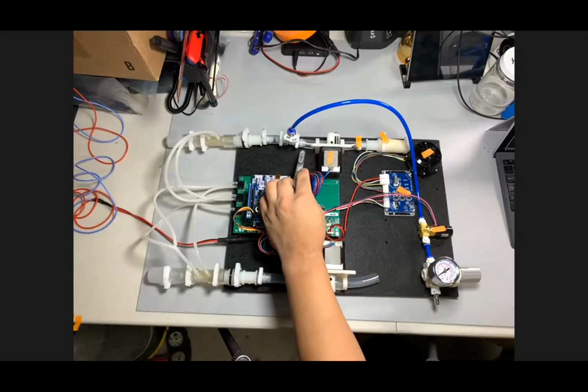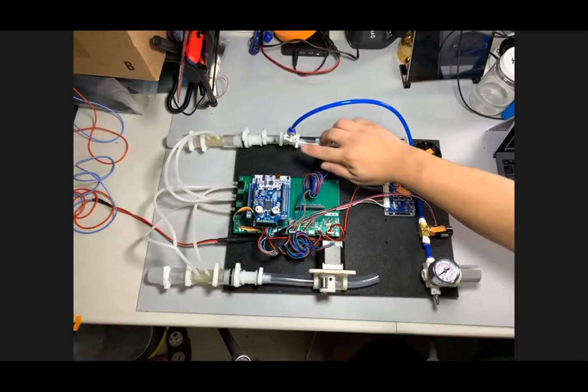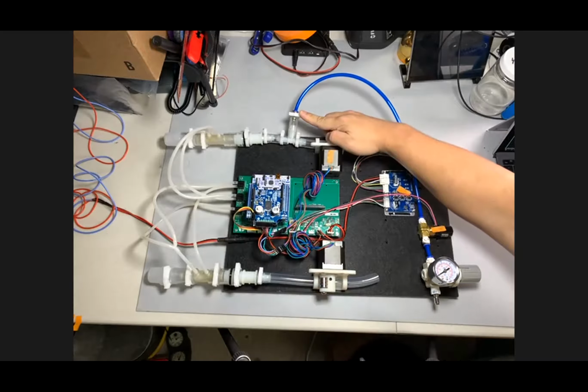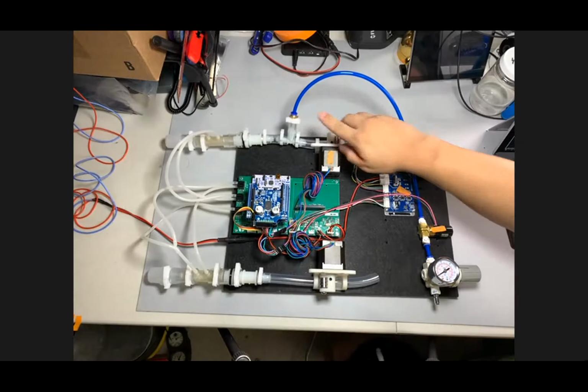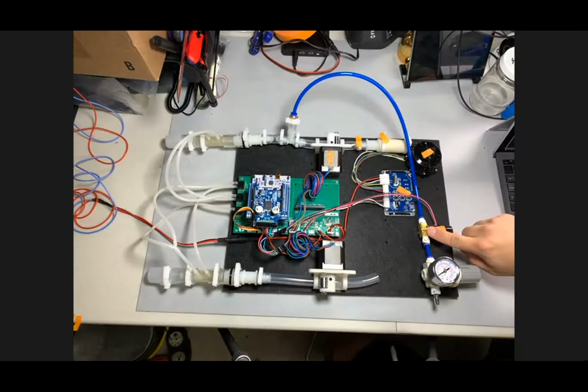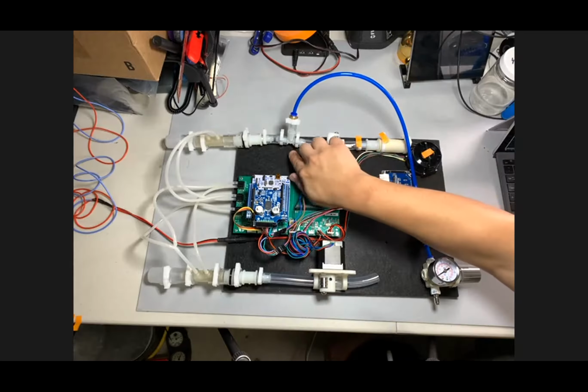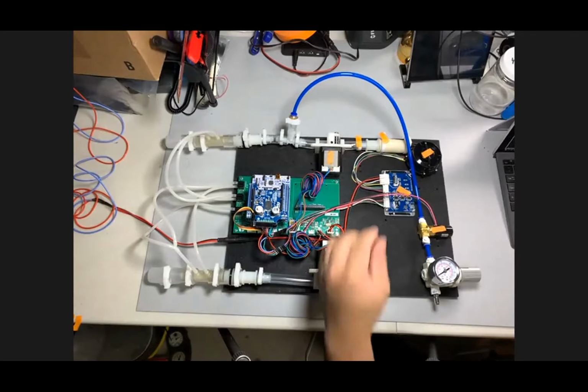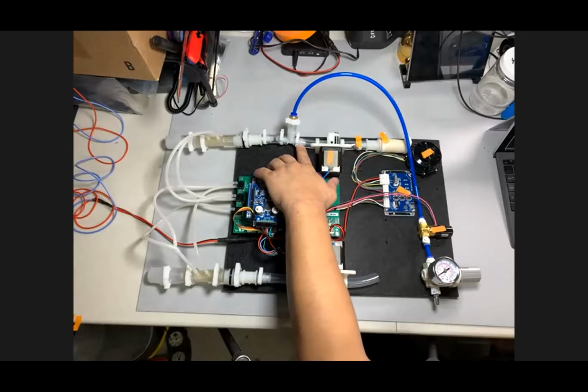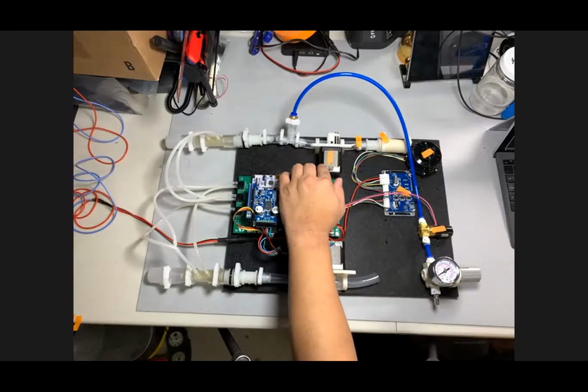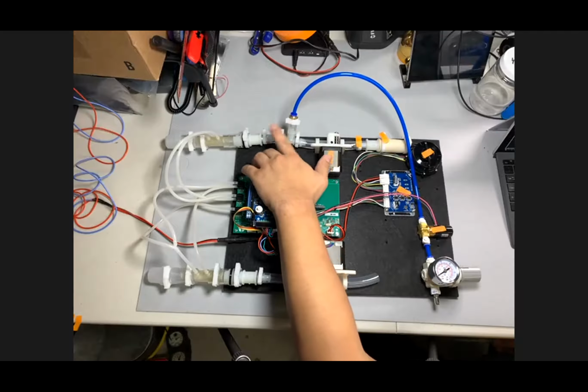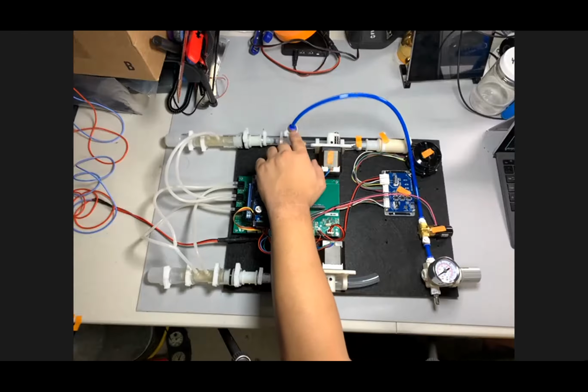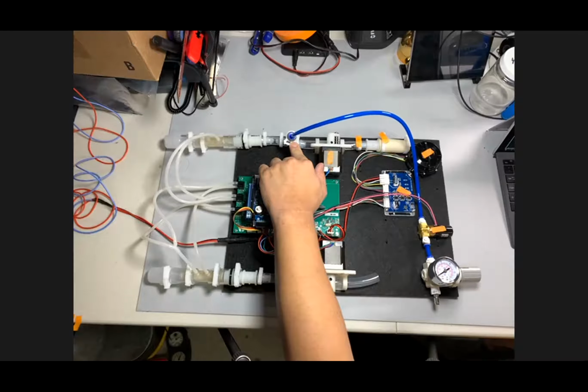Continuing on with the 5/8 outer diameter hose, we go to the mixing T. So this is essentially just a T-junction where the oxygen, which comes from the proportional solenoid, combines with the ambient air that's brought in by the blower and controlled by the pinch valve here. Now, this part of the design is still pretty new, and I think that, for example, this is just clamped in there. It's just a fitting that's been clamped in there.